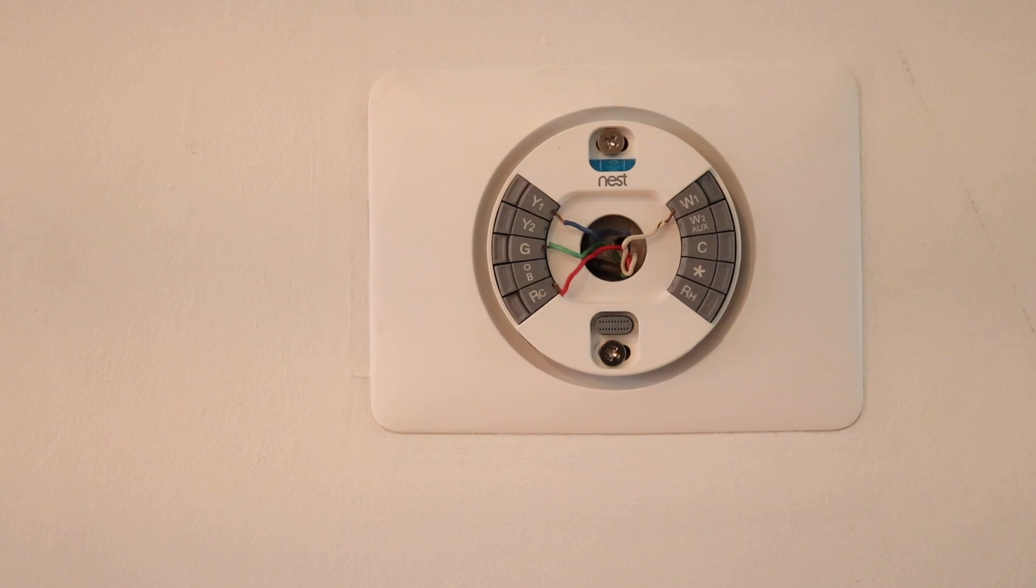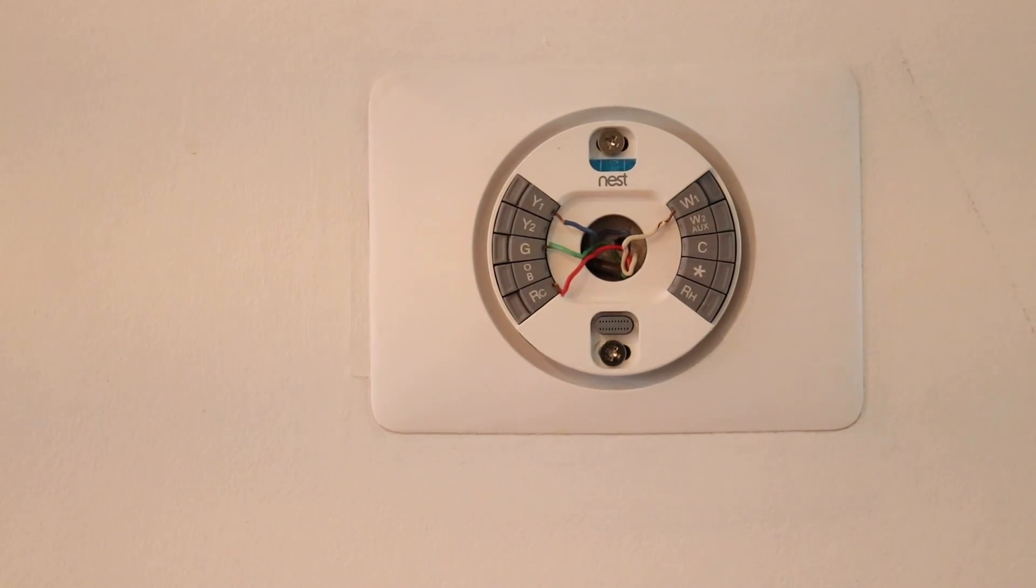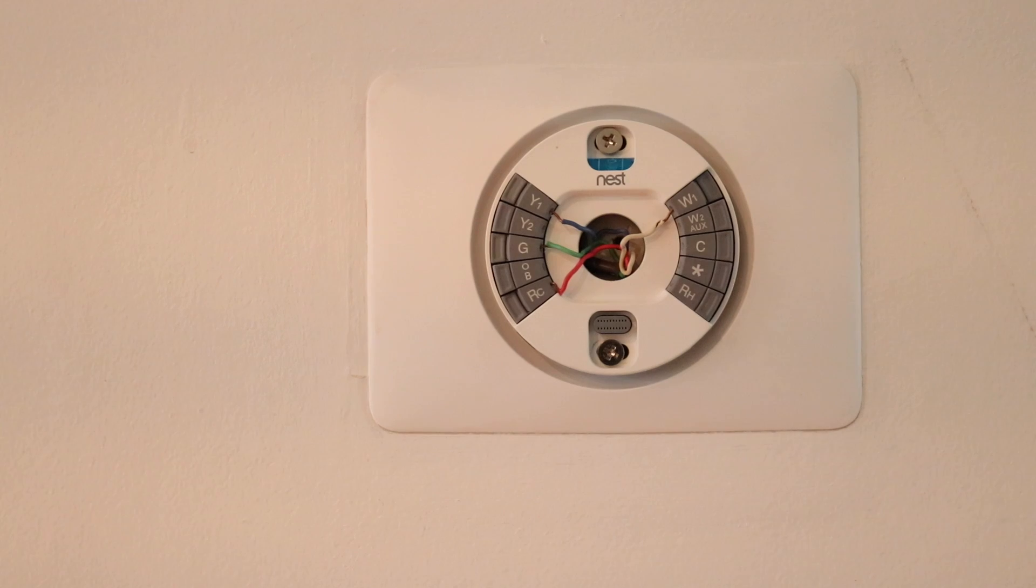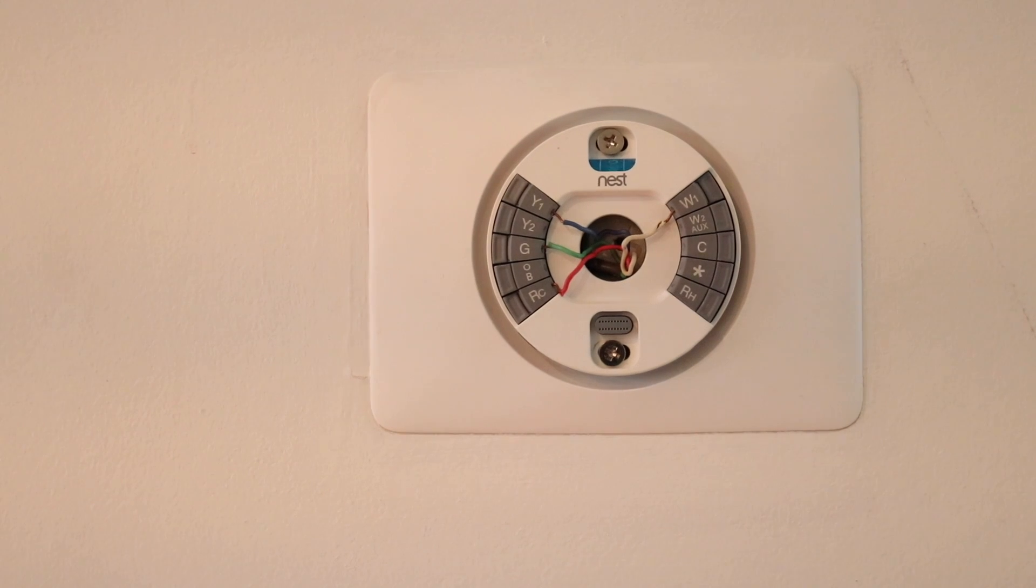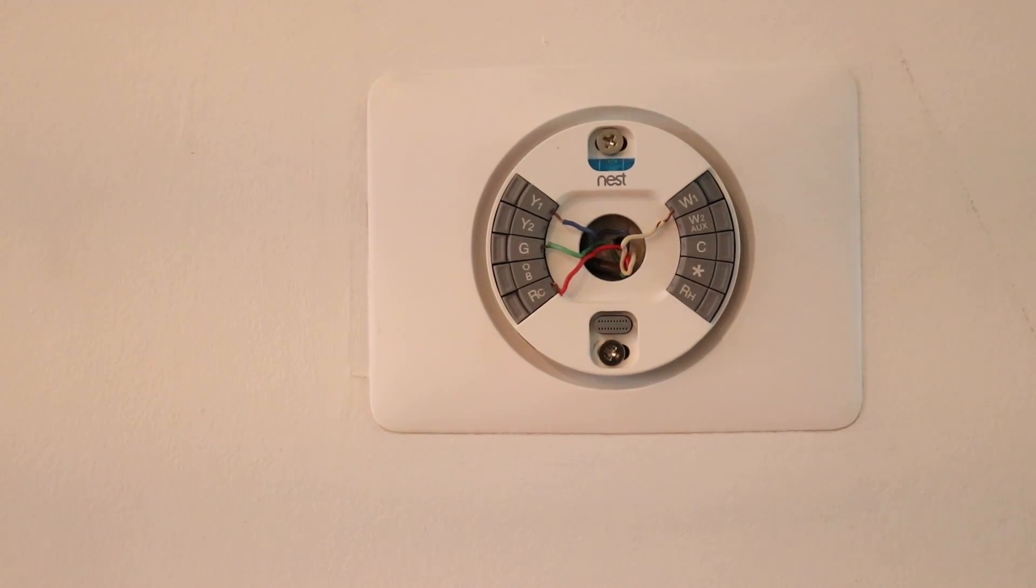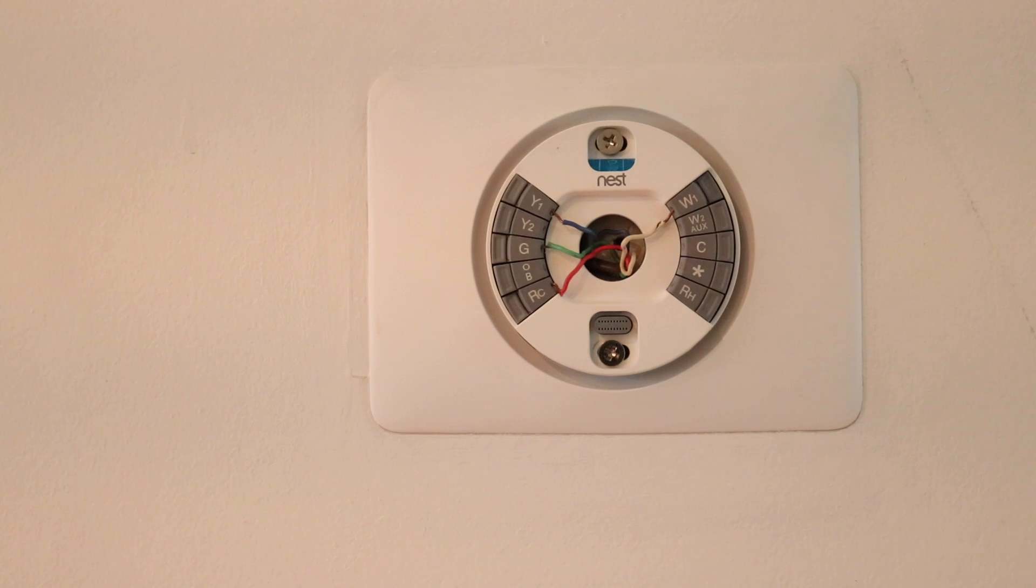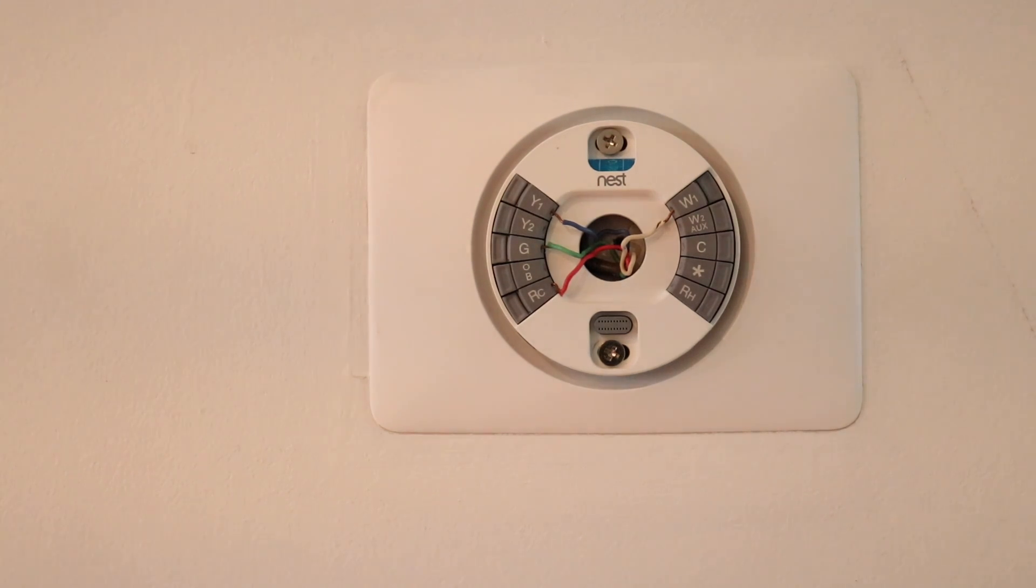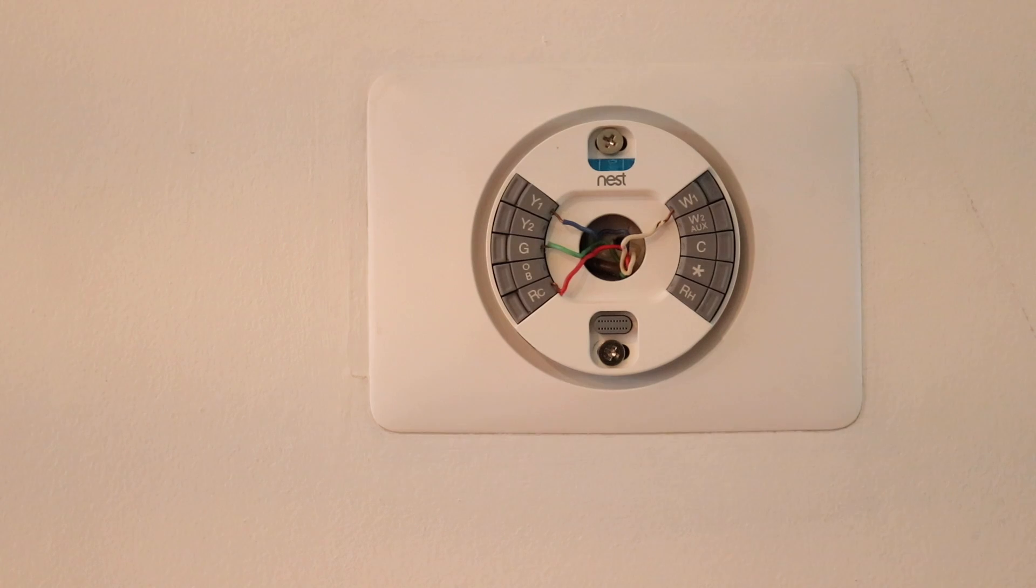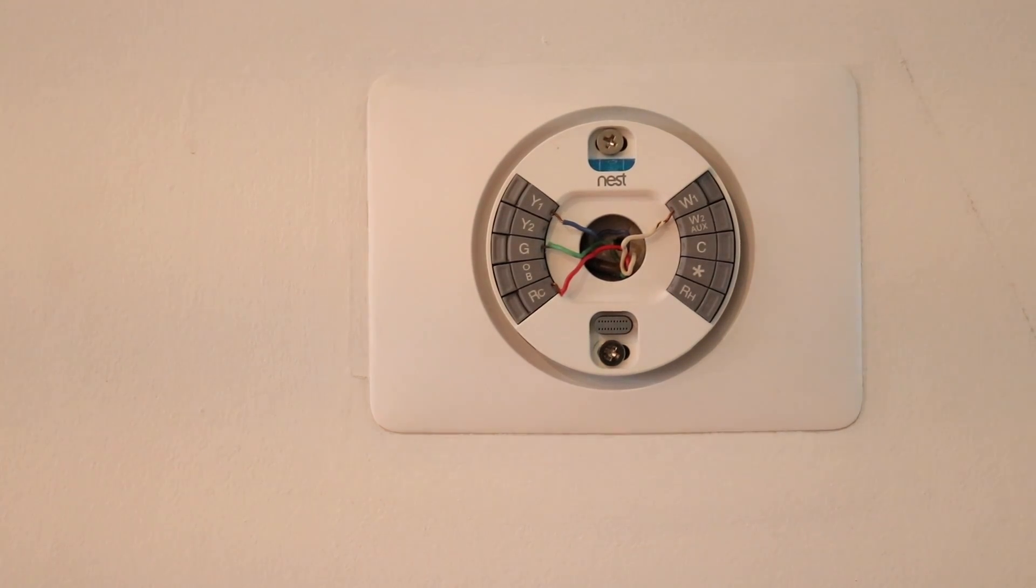So as we said, W1, that is heating. If you have a two-stage system, you're going to have W1 and W2. All W2 is, is the second stage of heating. So you might have a two-stage heating system. And what a two-stage heating system is, one level is low power. The second level is high power. It's just going to put out more heat.